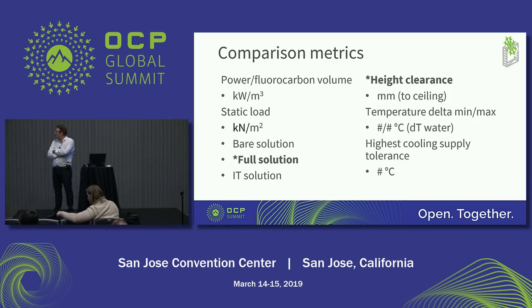So it's a function of junction temperature, inlet temperature of the fluid, and the flow rate. Basically, you need to have the relationship of the flow rate with different junction temperatures and the inlet temperature of the oil. So if you want to reduce delta, you'll have to increase the flow rate or lower the inlet temperature. There is no free lunch. You'll have to pay for the pump. And that is just specific to single phase.